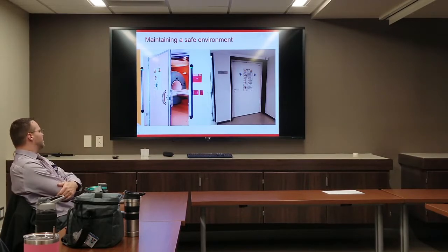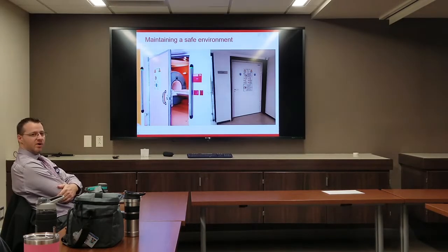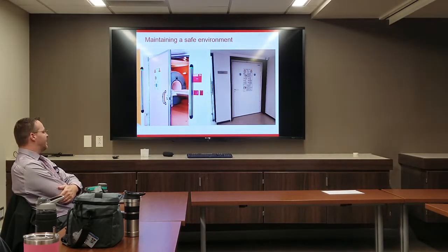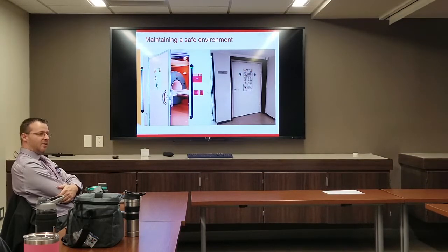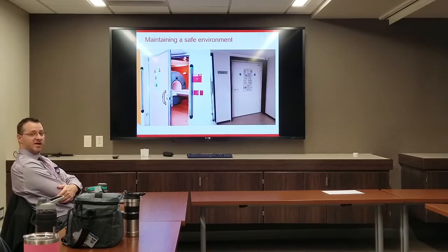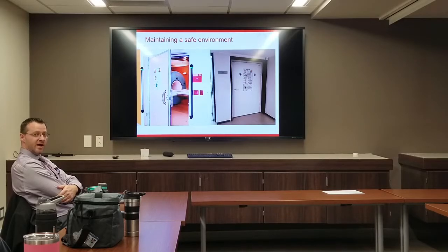For also maintaining a safe environment, depending on your area, there may be easy access to your main MR door. In that case, you'll want some type of locking mechanism where the door is locked but can be opened from the inside. I've been to places like this where the techs carry around a key for the door so they can get in, but no one else can open it — it just closes behind them.